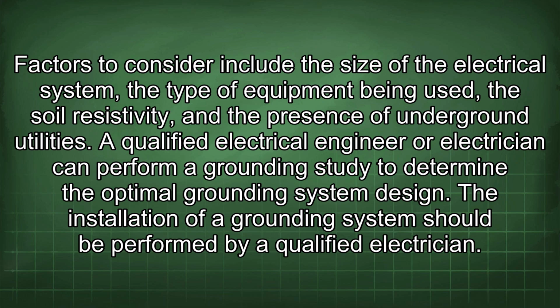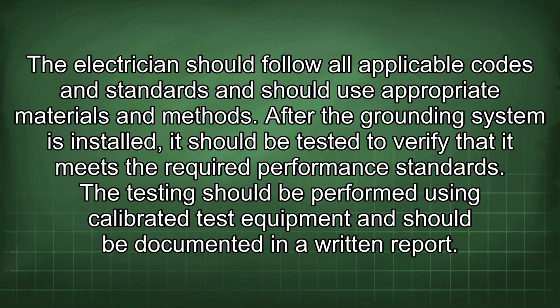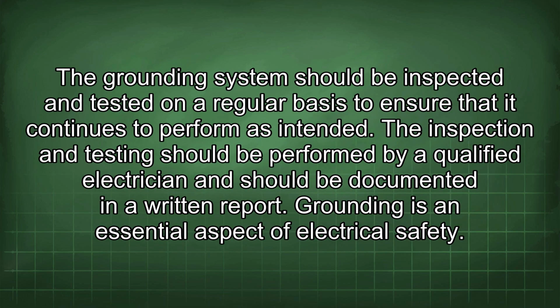The installation of a grounding system should be performed by a qualified electrician. The electrician should follow all applicable codes and standards and should use appropriate materials and methods. After the grounding system is installed, it should be tested to verify that it meets the required performance standards. The testing should be performed using calibrated test equipment and should be documented in a written report. The grounding system should be inspected and tested on a regular basis to ensure that it continues to perform as intended. The inspection and testing should be performed by a qualified electrician and should be documented in a written report.